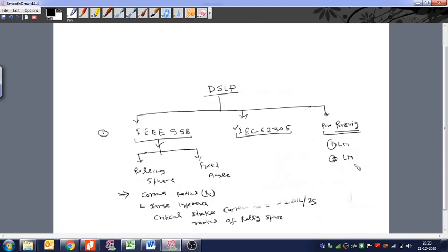In 2 LM method we calculate the combined radius of protections, and we take one imaginary element on the center of both elements, and we find out the midpoint protection height and the radius. If some part left, then we go on the 3LM method.